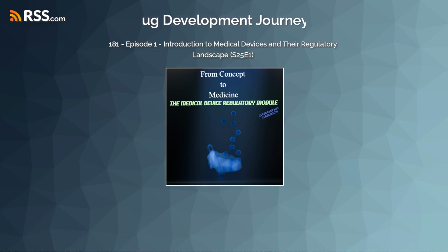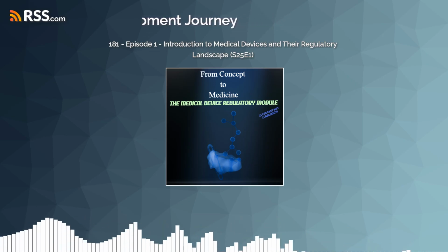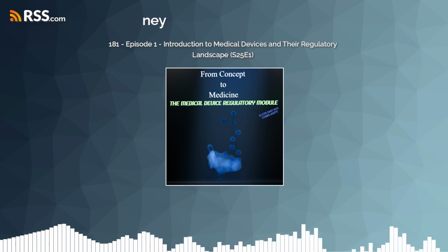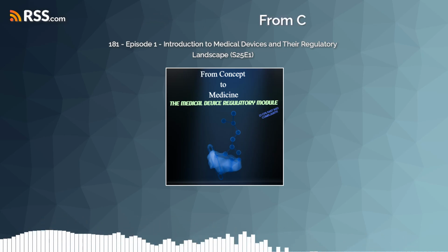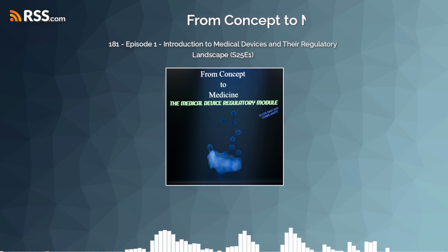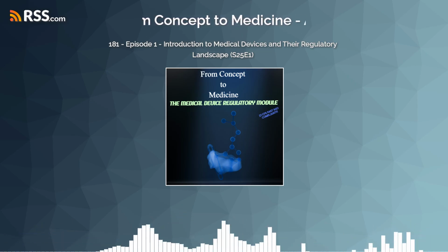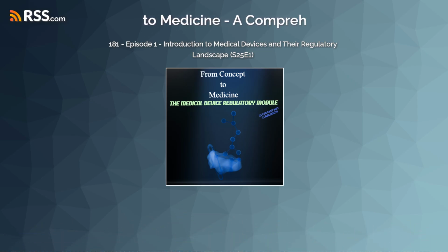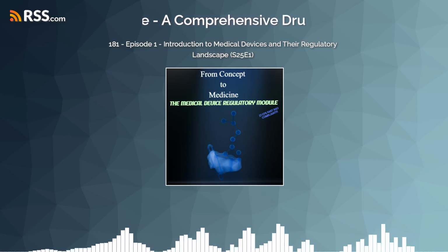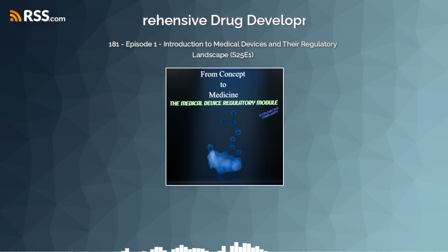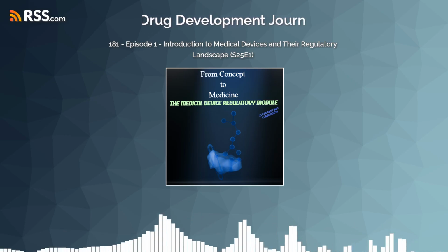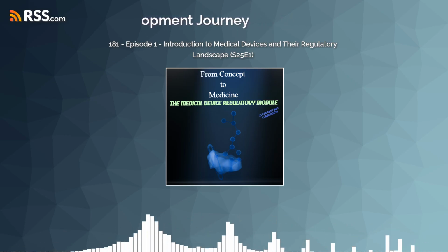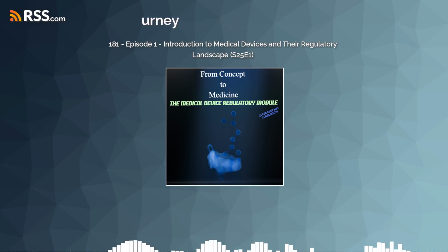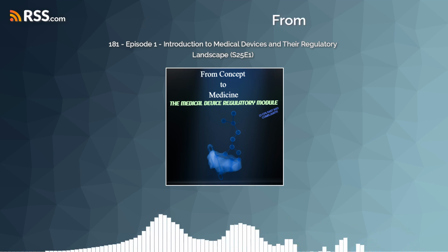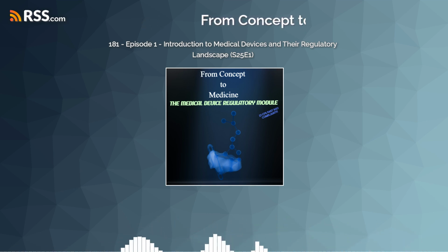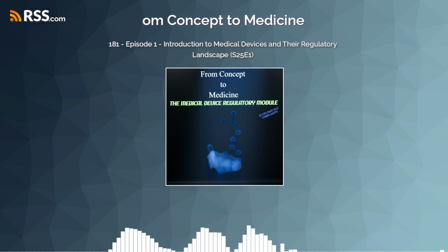Got it. I've also heard about post-market surveillance, where companies might be required to actively monitor devices after approval. How does that fit into the QMS? Right. Sometimes the FDA requires manufacturers to conduct post-market surveillance studies, often through what's called a 522 order under 21 CFR Part 822. This usually happens for higher-risk devices or when specific long-term questions remain after approval. It's about proactively monitoring the device's performance and safety in the real world across a broad patient population.